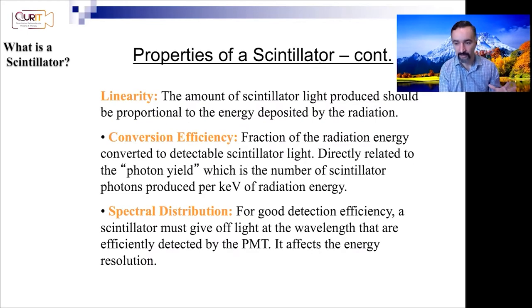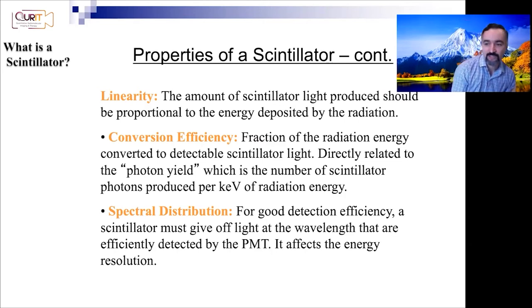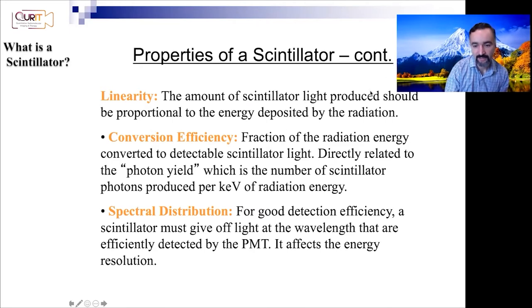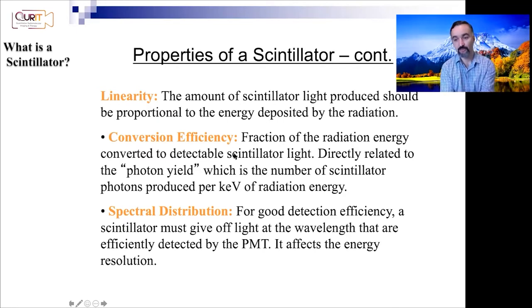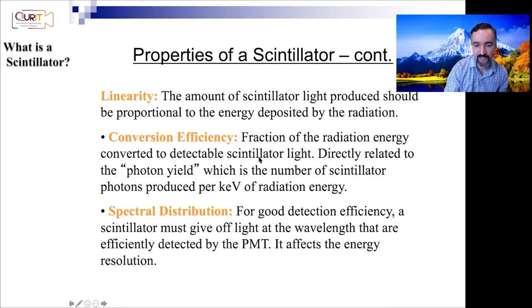You want these scintillators to be fast — to quickly register when an event is arriving — and a smaller decay time means smaller dead time. Linearity is important: the amount of scintillator light produced should be proportional to the energy deposited by the radiation. Conversion efficiency is also very important — the fraction of the radiation energy converted to detectable scintillator light, also referred to as photon yield. The spectral distribution matters too, so that light is emitted at wavelengths effectively detected by PMTs.